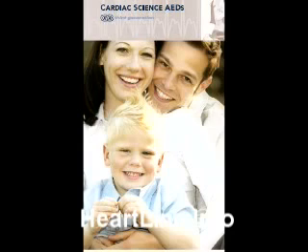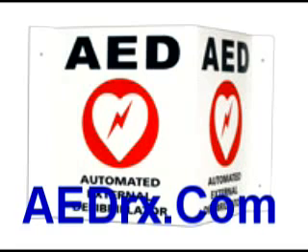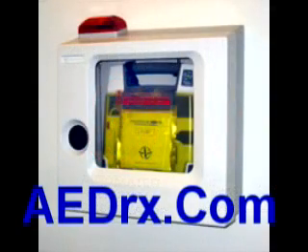Every pad uses a water-based gel, and out of those 3 components, this is the most critical component of all because this connects the AED to the victim. And the problem with the pads, every AED uses a water-based gel pad, and over time, these water-based gel pads will dry up. So we always want to make sure that the pads are in functioning order.